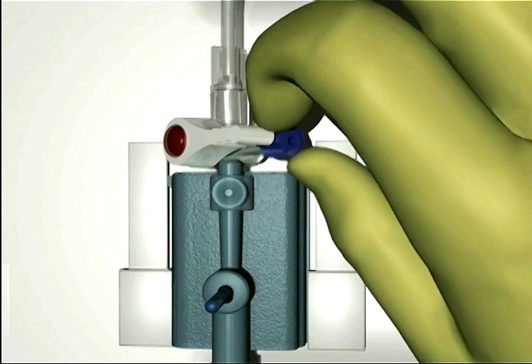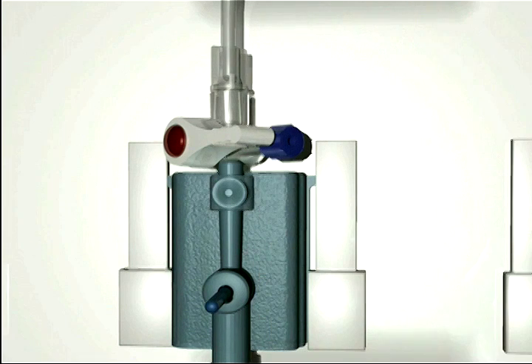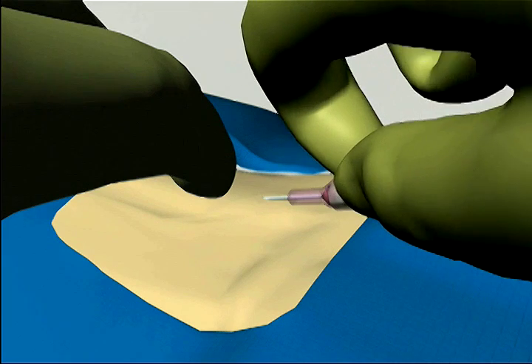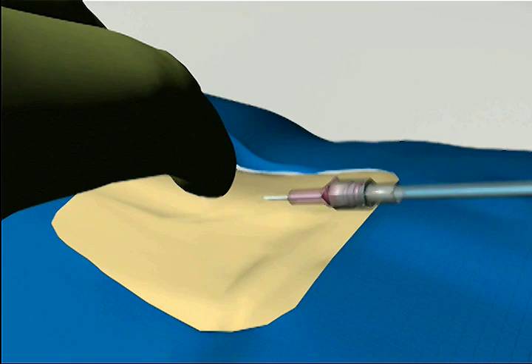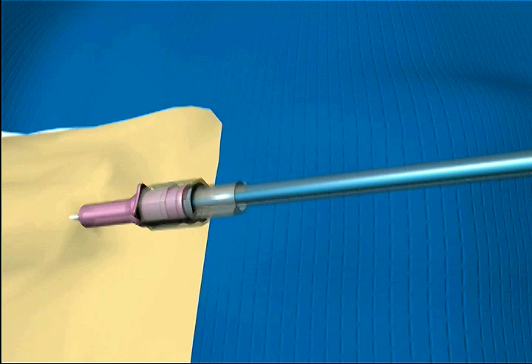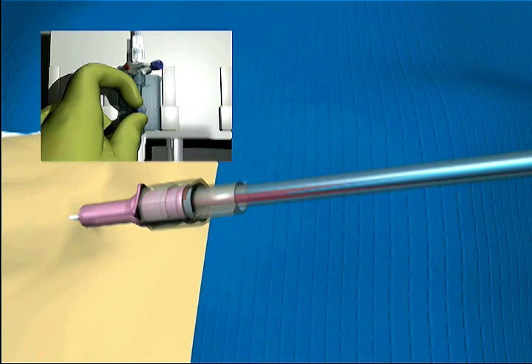Step 6. If not already connected, connect the TruWave pressure tubing to the patient's catheter. Aspirate the line to assure no residual bubbles remain, as well as confirming patency of the catheter. Then flush the system of any residual blood.